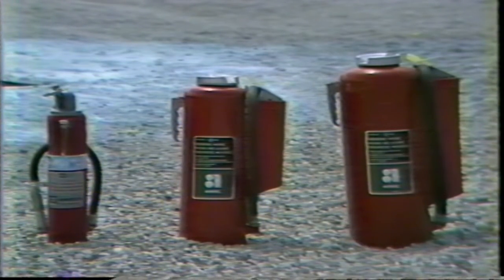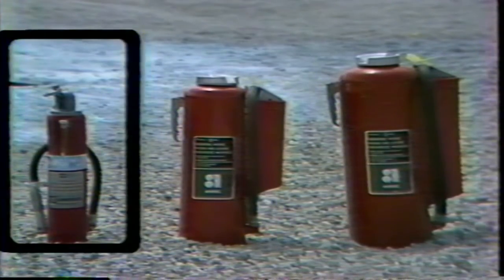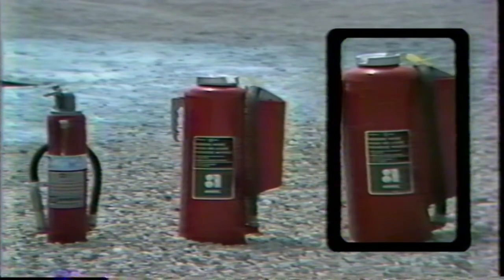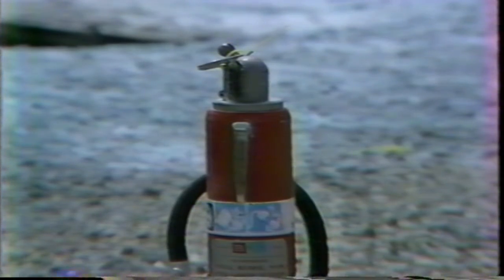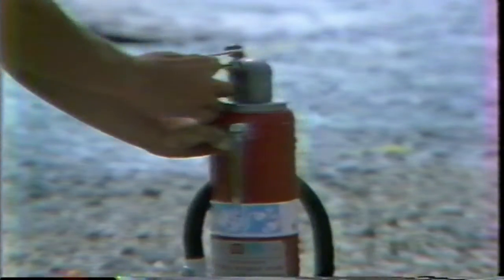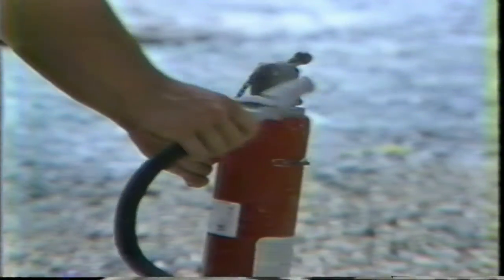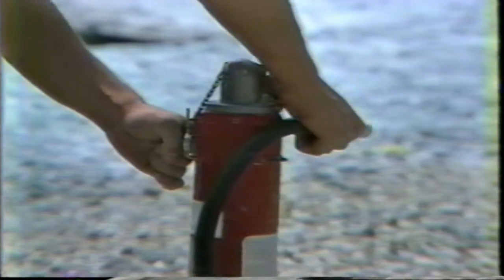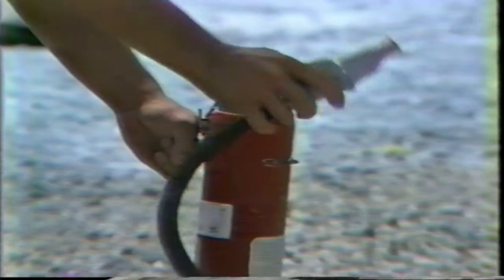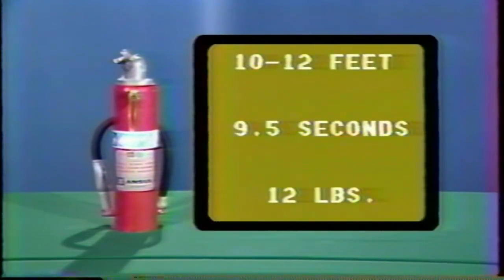At Union Electric Company, three sizes of cartridge operated units are used: the 5-pound dry chemical, the 20-pound dry chemical, and three models of the 30-pound dry chemical. To operate the 5-pound unit, remove the ring pin — this breaks the seal — then remove the hose and push all the way down on the puncture lever and release. The 5-pound dry chemical unit is rated at 10BC, capable of putting out 10 square feet of burning flammable liquids. The extinguisher is expected to last 9.5 seconds and has a range of 10 to 12 feet. Total weight of the unit is 12 pounds.